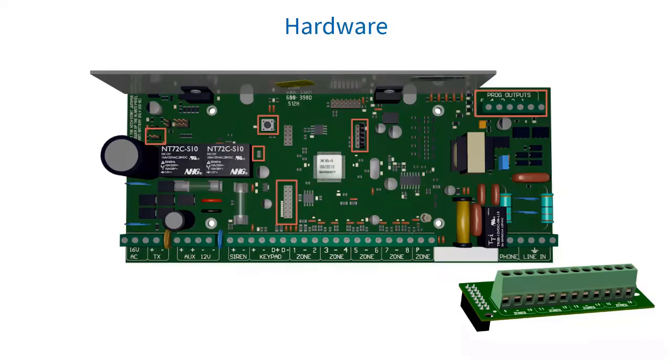We have our programmable outputs, which all sit on the top right side of the board, and can supply 80 milliamp of current. By default: output one will pulse if a panic or duress is triggered; output two will pulse if a burglary condition is triggered; output three will latch on when the system is away armed; output four will pulse if a burglary condition is triggered; output five will pulse if a fire condition is triggered; and output six will pulse if a medical condition is triggered.